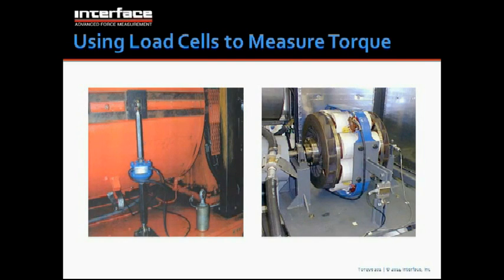Again, certain installations lend themselves to this more than others. These eddy current dynamometers were designed specifically to be mounted that way. If you have a big electric motor that's mounted on a plate, it's a little harder to gimbal it like this. Also, if you have a situation where you want to measure torque, imagine like a big pipe you're trying to screw into another pipe, you want to measure the torque. It may be difficult to imagine a way you could do that with a torque sensor, but you can actually do it by using one or multiple load cells and applying a force at a distance from the center line.